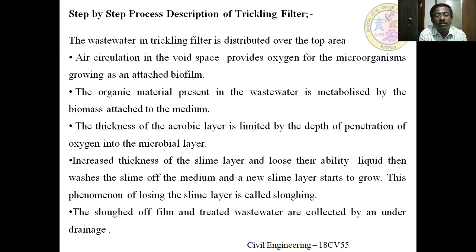As the slime layer increases in thickness, it loses its ability to hold on, and the liquid then washes the slime off the medium, and a new slime layer starts to grow. This phenomenon of losing the slime layer is called sloughing. It means once the thickness of the film on the media goes on increasing, usually at the outer surface aerobic digestion takes place due to the availability of oxygen.